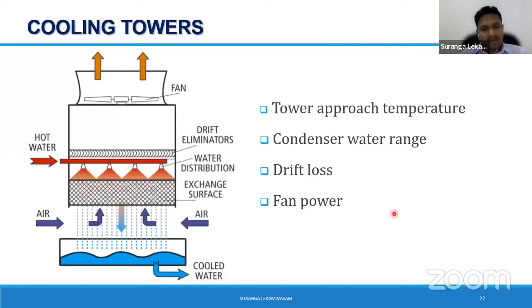Then fan power. Fan is the only element which consumes power. But again, you have to specify this because if you don't specify the fan power, the supplier will give you a very inefficient cooling tower. Simply, fan power is basically related to the fan airflow rate and the friction loss. Friction loss is the loss that happens for the air coming through the infill. So if you have a very tight infill and a small cooling tower, your friction losses are very high, and that leads to a bigger fan motor. But if you increase the cooling tower size and infill, then your frictional losses are less. Eventually, your fan power absorption is also less. So unless you specify this to minimize the cost, the supplier may give you a very tight cooling tower, which consumes a very high amount of power.